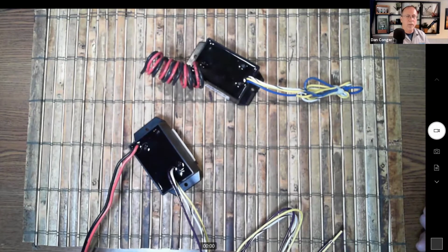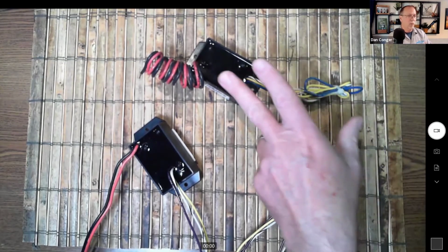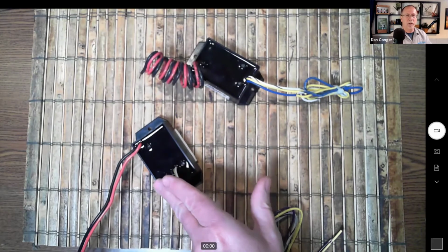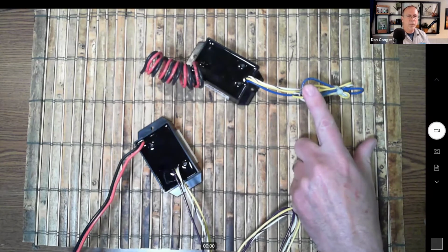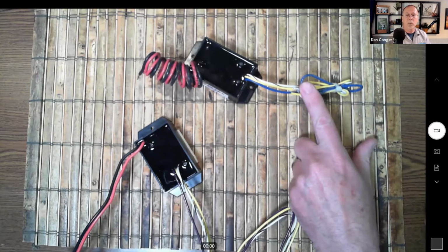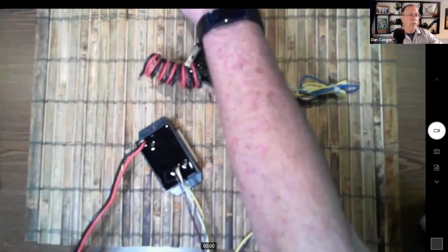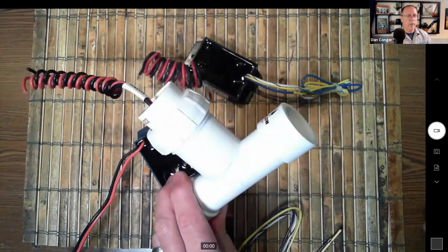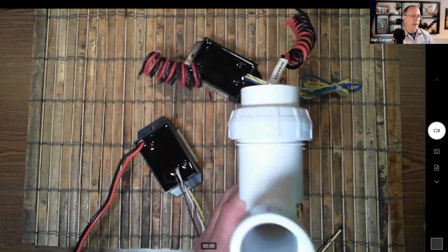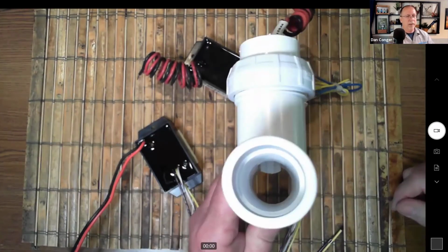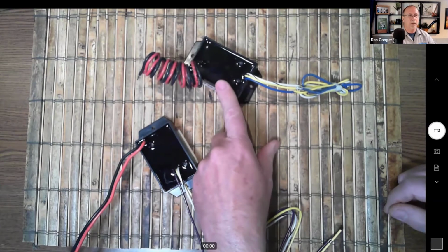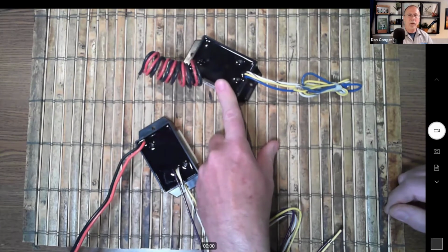Right. Okay. So the question that we were kind of working on, and the burning question is, when do I use a 5308 and when do I use a 5309? Okay, let's see if I got this. The 5308 is going to be for a lot of the meters that don't need power. So that's going to be most pulsed output. Now this one already has a flow bicoder in it, but if I have a paddle style that doesn't need any additional power, the 5308 is going to cover it for many, many circumstances. But devices that need power that are not self-powered. Most, yeah. Majority.